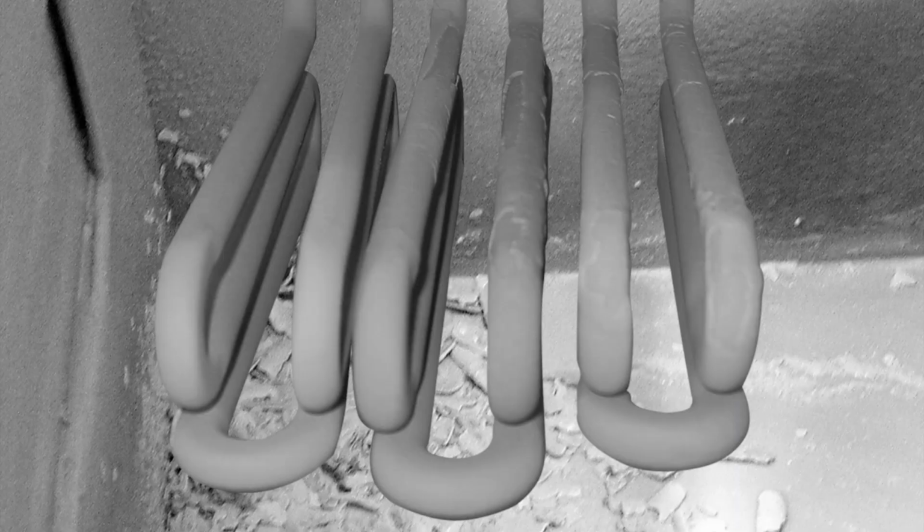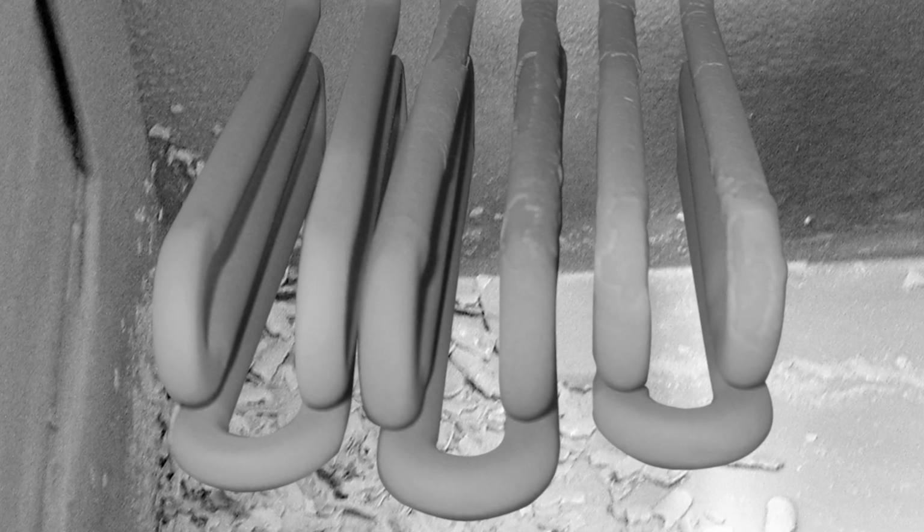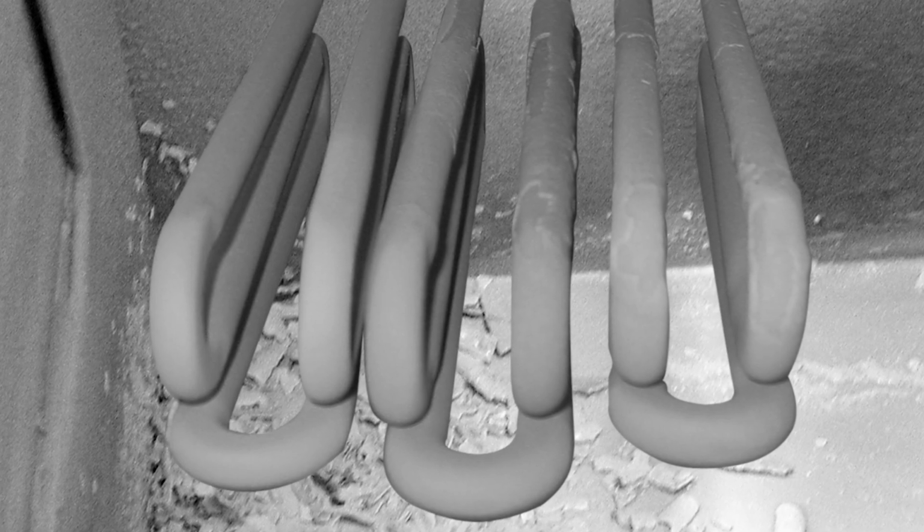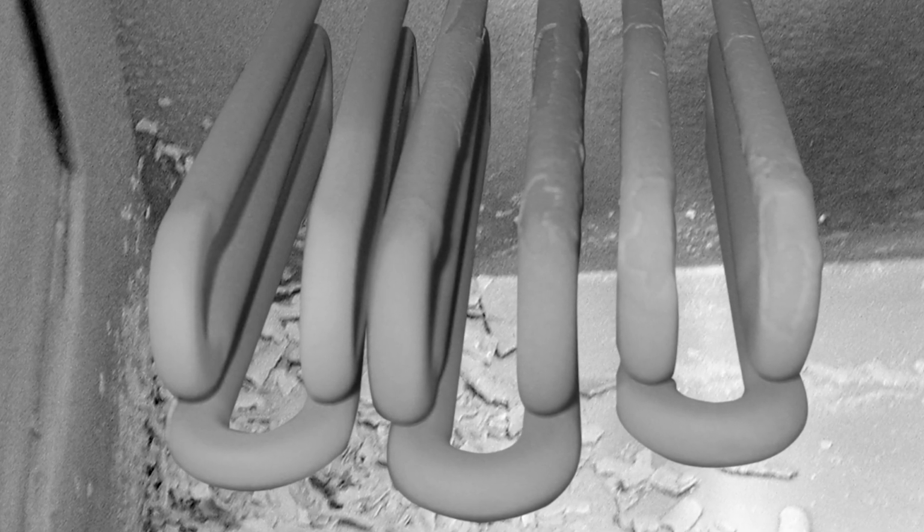Well, if we are talking about making steam initially, you've got a steam generator. The harder the water, the more mineral deposits will be left behind, because it is the water vapor that leaves and the minerals stay behind. And how you deal with that maintenance, if you've got a large tank, maybe it can collect for quite a bit, but if it collects for some time, it's hard water, it starts to coat the heat exchangers or heating elements, as an example, causing inefficiency. It's not going to be able to transfer into the water, which is what you want to cause that phase change.